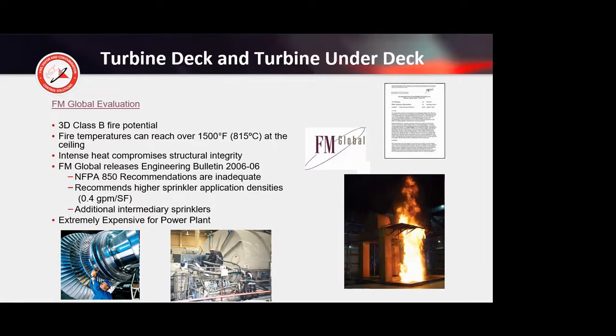So they came back and said the recommendations that are found in NFPA 850 are inadequate. They recommended a higher sprinkler density of 0.4 gallons per minute per square foot. So if you were already designed and you're at 0.3 and now you have to go to 0.4, that's a 33% increase in water. That's a major upgrade.